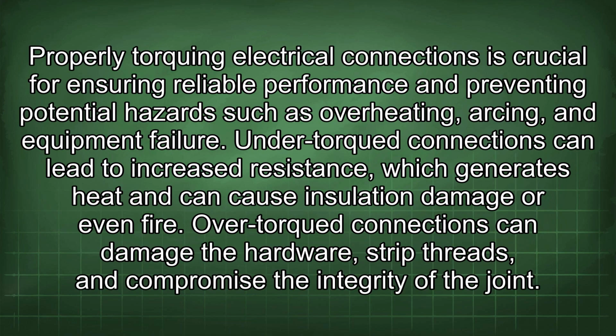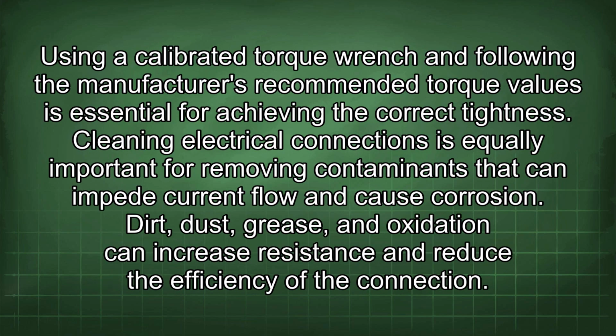Properly torquing electrical connections is crucial for ensuring reliable performance and preventing potential hazards such as overheating, arcing, and equipment failure. Under-torqued connections can lead to increased resistance, which generates heat and can cause insulation damage or even fire. Over-torqued connections can damage the hardware, strip threads, and compromise the integrity of the joint. Using a calibrated torque wrench and following the manufacturer's recommended torque values is essential for achieving the correct tightness. Cleaning electrical connections is equally important for removing contaminants that can impede current flow and cause corrosion. Dirt, dust, grease, and oxidation can increase resistance and reduce the efficiency of the connection.